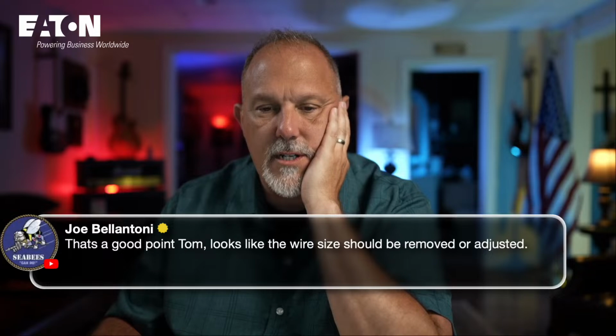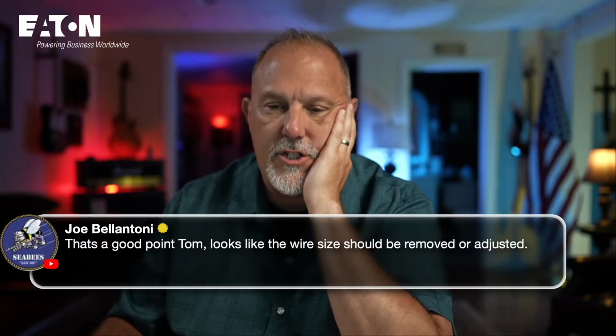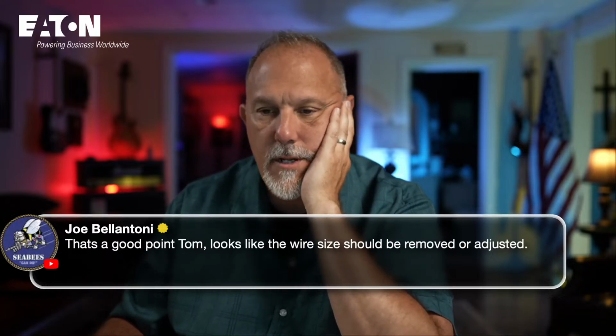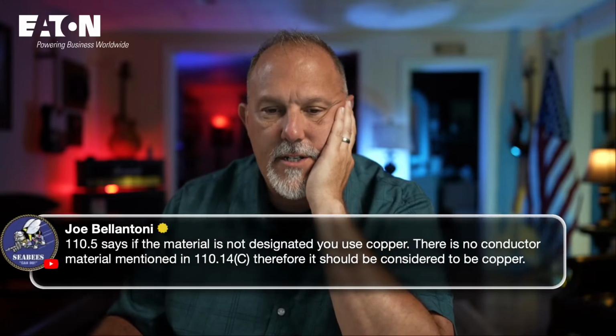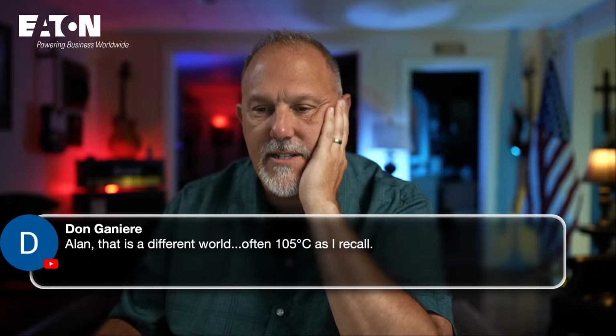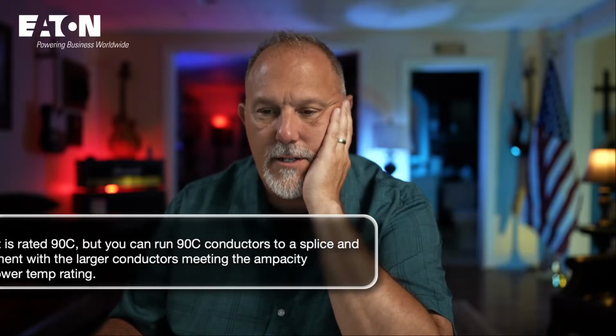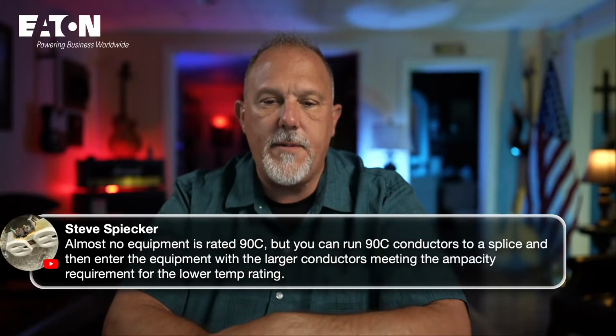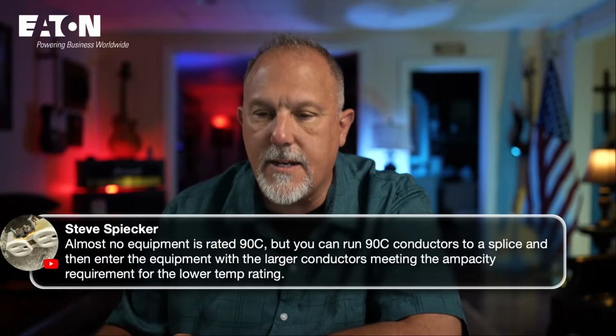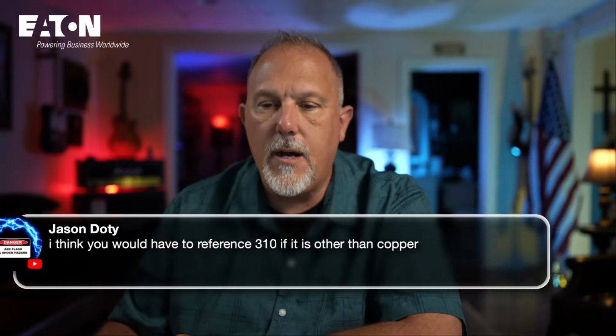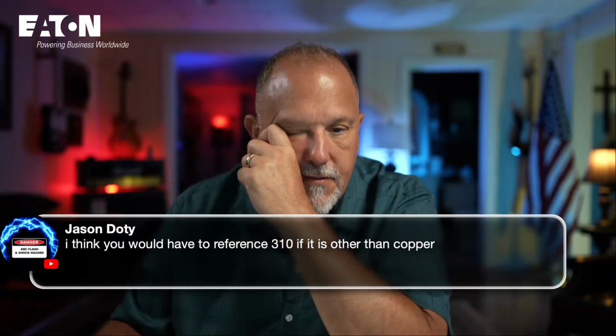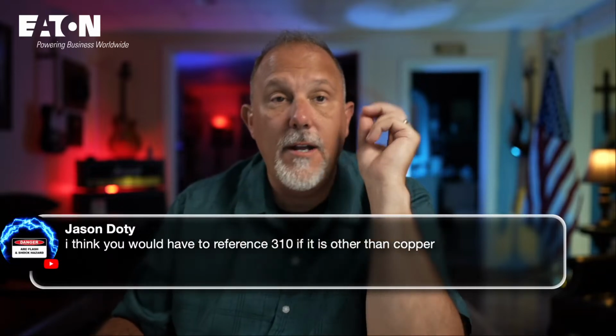That's a good point, Tom. Looks like the wire size should be removed or adjusted. Hold on, I got to see where I was at. See that? 110.5, materials not designated as copper. There is no copper. Okay, I remember that discussion. Alan, that's a different world. 105 degrees C, as I recall. That is correct, Dawn. Steve says almost no equipment is rated 90 degrees C. Okay, we were talking about the 90 degrees C. I'm with you. I think you would have to reference 310 if it's other than copper. Yes, and that's what I did, Jason.